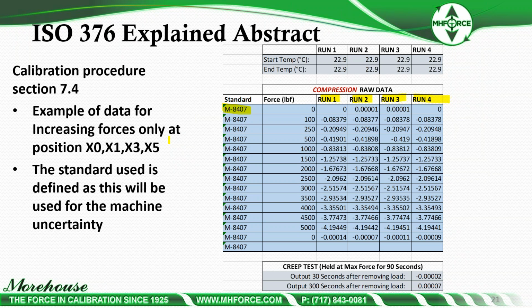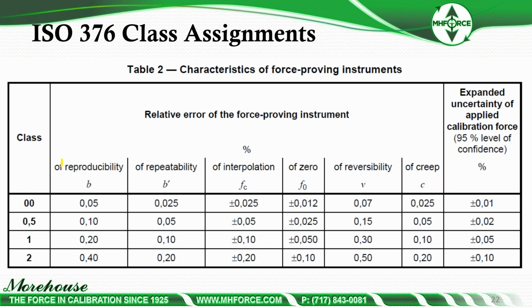ISO is very interesting in the data analysis section because it tests the device for numerous things. This is directly from the standard, Table 2, characteristics of force proving instruments. We test for reproducibility. We test for repeatability. We test error of interpolation. We test error of zero. And then here's reversibility, but remember, reversibility is only if the instrument is going to be used to take descending measurements. If it's not used to take descending measurements, then you do a creep test instead. So this is really one or the other.